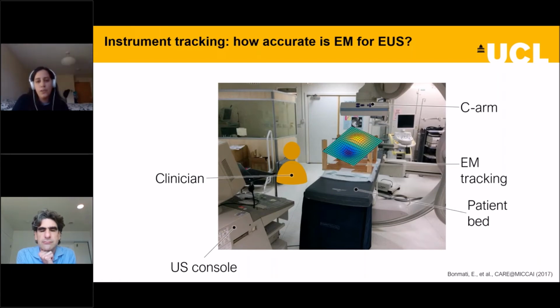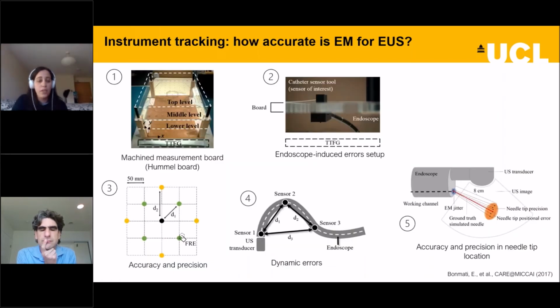So our first study was to evaluate the accuracy of the tracking system. We used a custom-made machined measurement board, which we also call a Hummel board, and a structure that would allow us to place this board at 3 different levels, which is shown in picture number 1. We also created a series of adapters to fix the endoscope and sensors on this board, which is shown in picture number 2. And finally, we found the precision and accuracy by analyzing the positional information of the sensors inside the endoscope at each position on this grid.